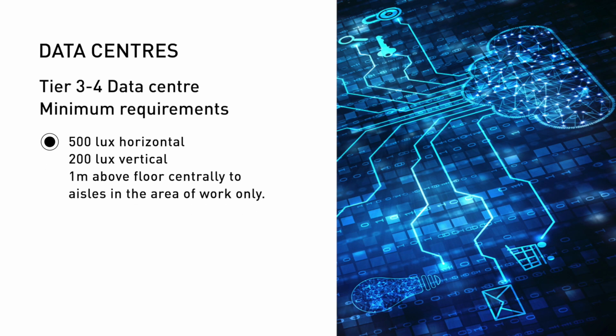So what determines what the tier level is for a data centre? That's a little bit more complex, but that's more to do with the level of security that the data centre is providing. The data centre will be designed to a particular tier, and that will then impact us on the lighting aspect and what the minimum criteria are. But the criteria on tier 2 is relatively low. Tier 3, a little bit more complex, but nothing too difficult. In terms of lighting levels, you talk about 500 lux on the horizontal, 200 lux on the vertical at a metre high, and these are to the aisles where the area is worked on only. So going back to the hot aisle, cold aisle, generally in the cold aisle only. But as I said earlier, ideally no people.